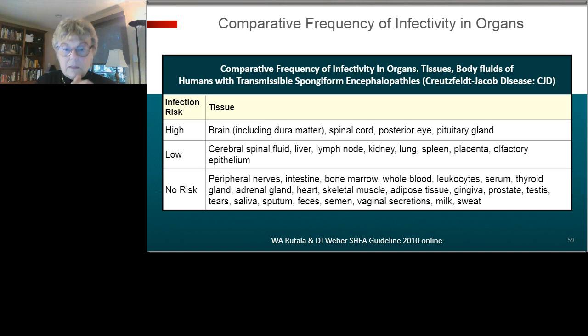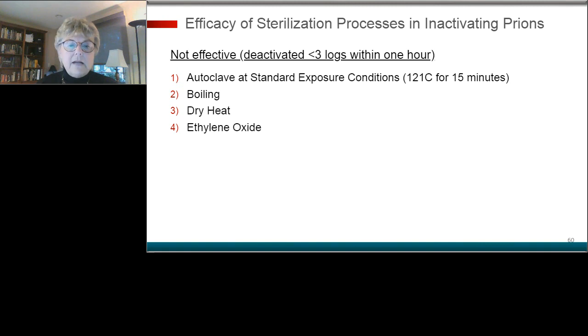Okay. So, effectiveness of sterilization processes in inactivating prions. This is to really respect this infective protein. Not effective, deactivating it's less than 3 logs effective, so it's really not doing enough that it needs to do within 1 hour. And that would be the autoclave at standard exposure conditions for 15 minutes in this case. Boiling, dry heat, ethylene oxide, formaldehyde, hydrogen peroxide gas plasma with Sterrad. This particular study was done with a Sterrad.